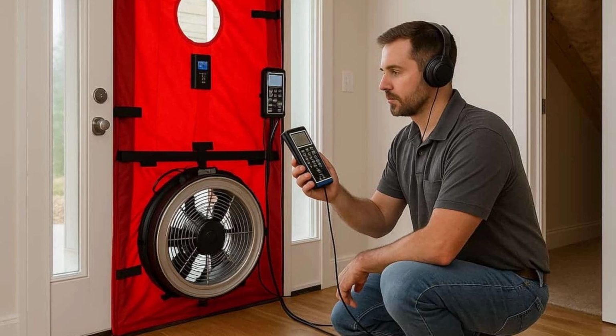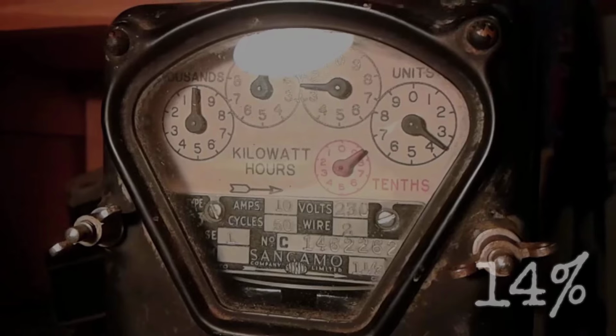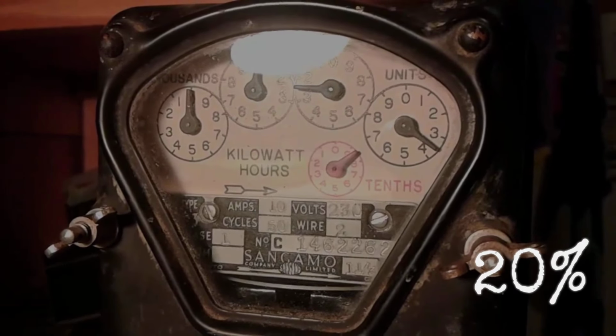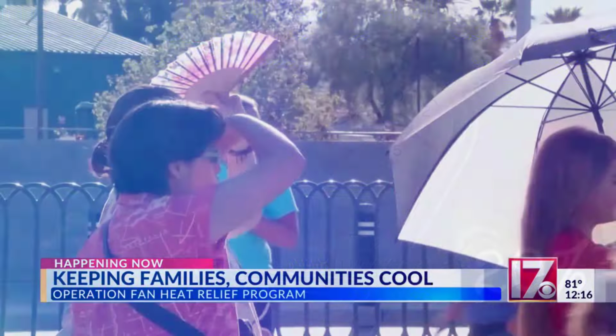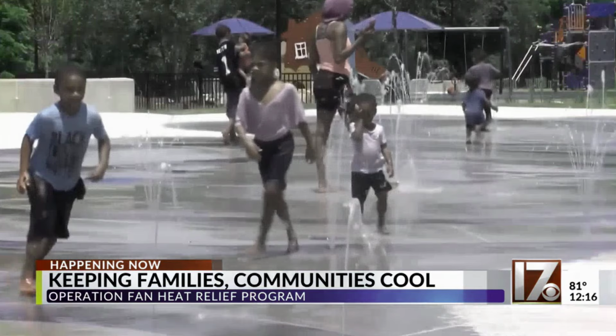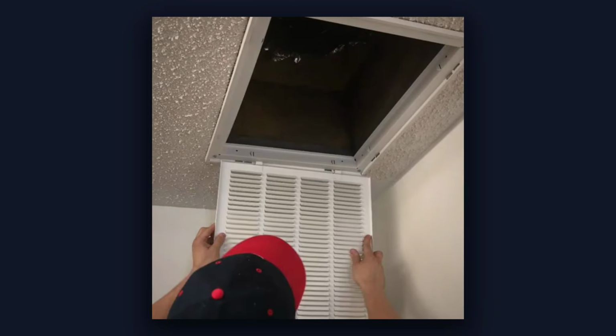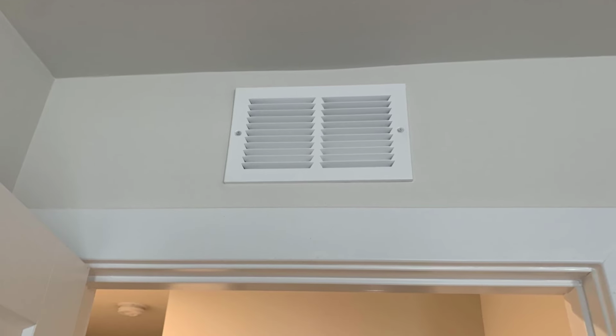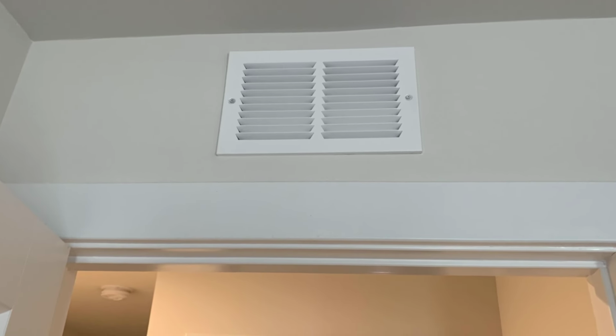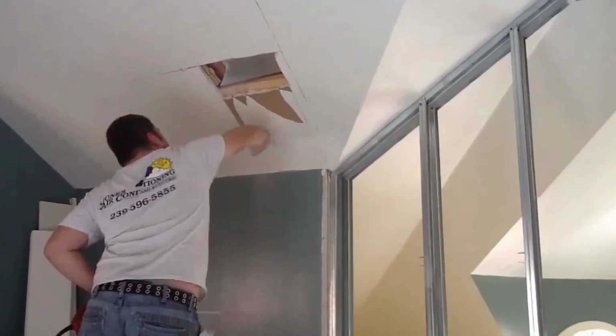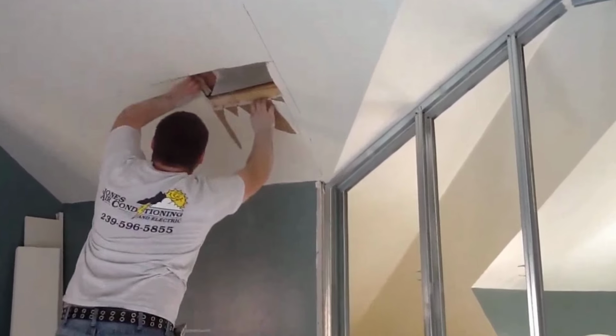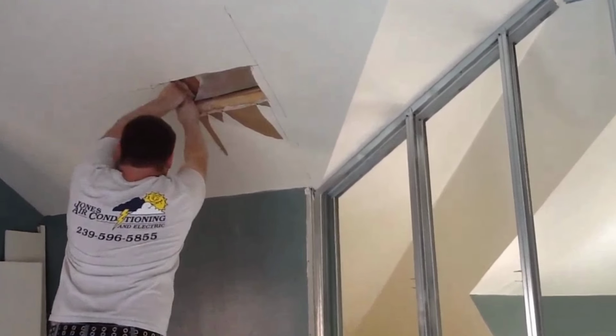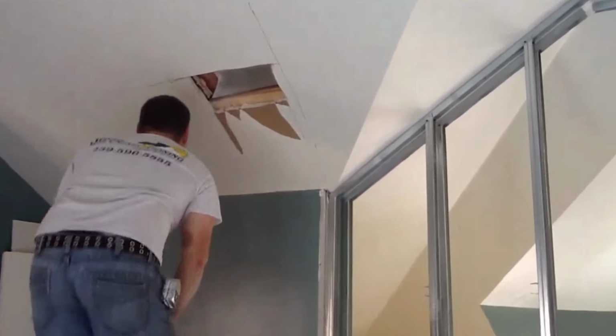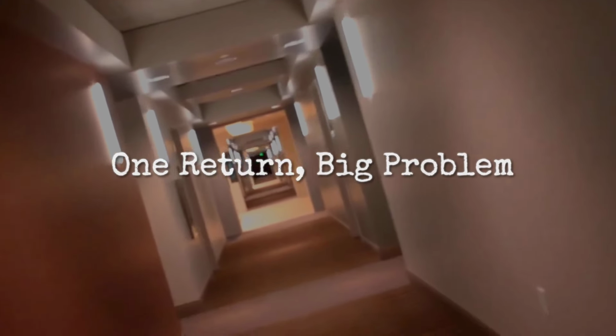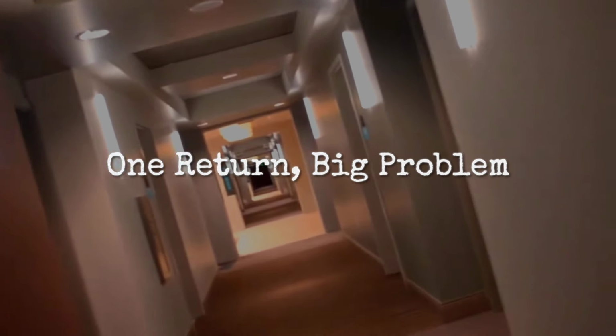When your doors close, your rooms pressurize. The system starves for return air and works much harder. Your bill will go up. Your comfort will go down. Technicians install dedicated returns in every major room or transfer grills above doors. The cost during construction is almost nothing. Retrofitting later means cutting walls, and builders often skip it because one return passes code. One more. Number 5 is the root cause behind everything else on this list.